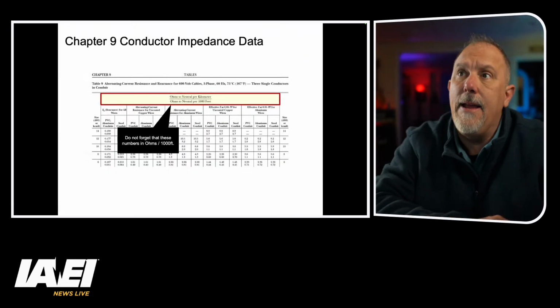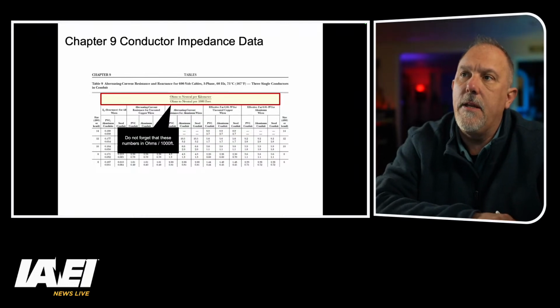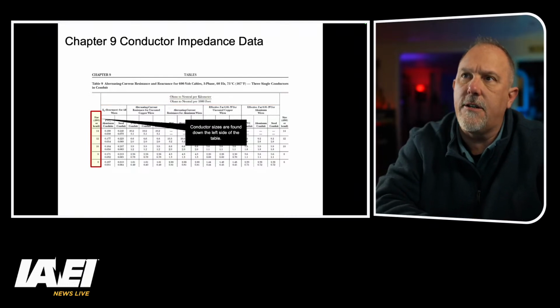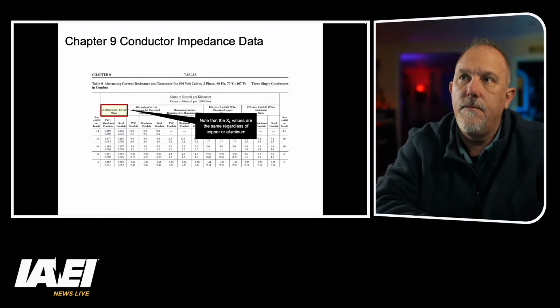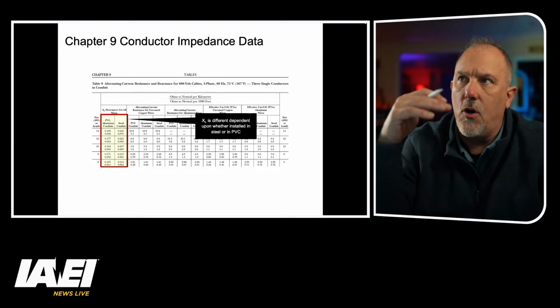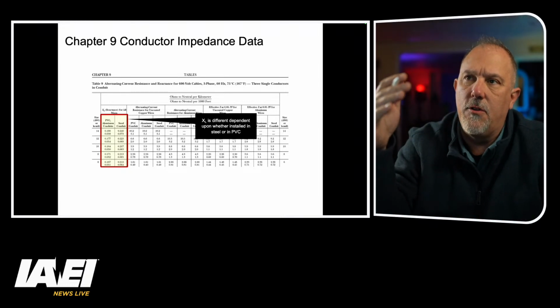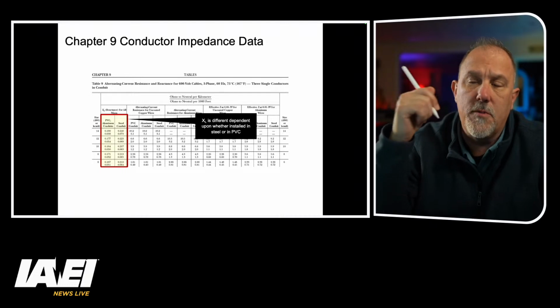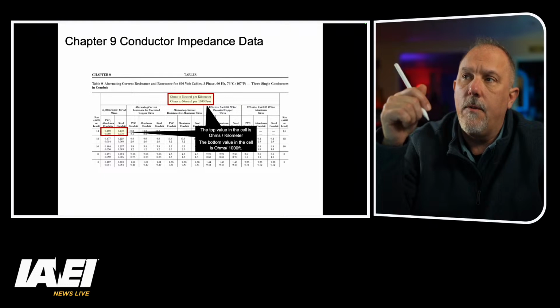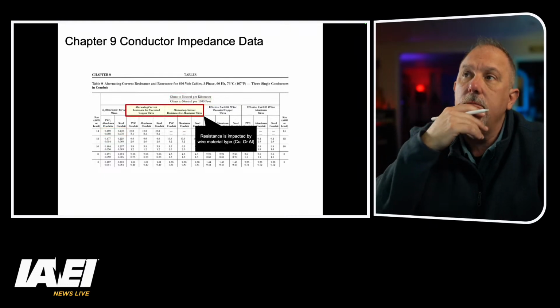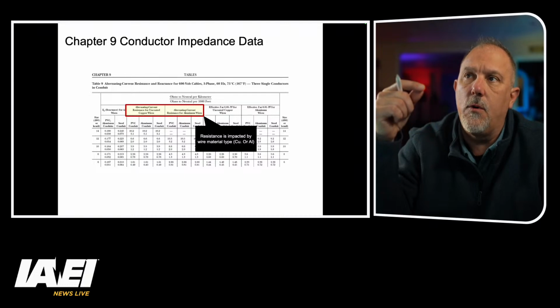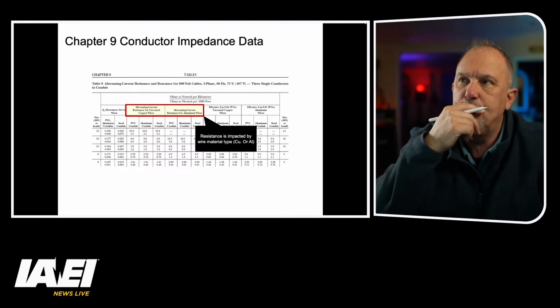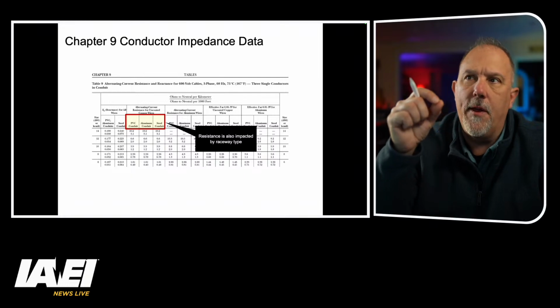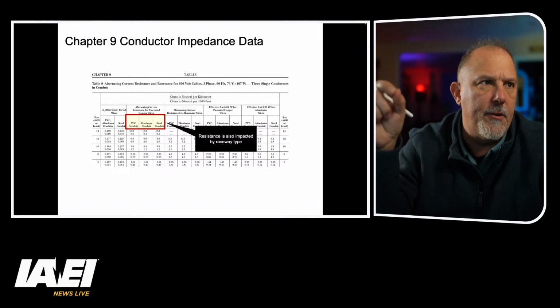So if I go to Chapter 9, Table 9, you'll see there is this value. For each of the sizes of conductors, you have a reactance, and you'll notice there's ohms per kilometer and ohms per 1,000 feet. So the bottom number is your ohms per 1,000 feet, right? Don't forget, use the bottom number. Then you have your resistance, and this is for copper wires or for aluminum wires, so you have different values for both. You also have to know whether it's in PVC, aluminum conduit, or others.